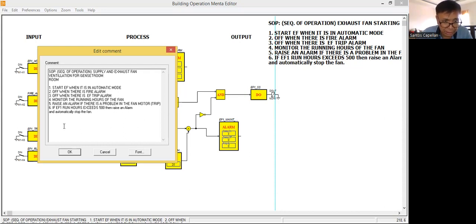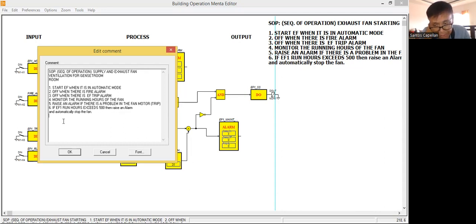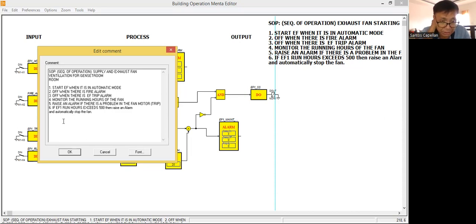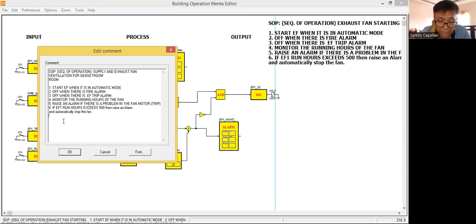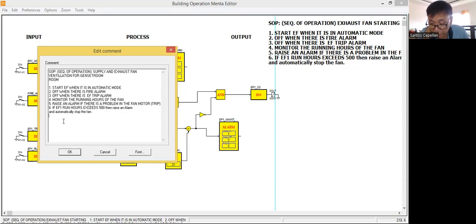Actually, in the Middle East, if you are going to join a building management system project, you will find this system. Because in a building, there will always be a standby power or standby generator set. There are some sequences of operation in a standby generator set, especially related to the fire alarm system. For the BMS, it will be the one to control the operation of the supply fan and the exhaust fan. We need the supply fan to supply fresh air inside the room, and the exhaust fan will vent out the hot air generated by the generator set when it is running.